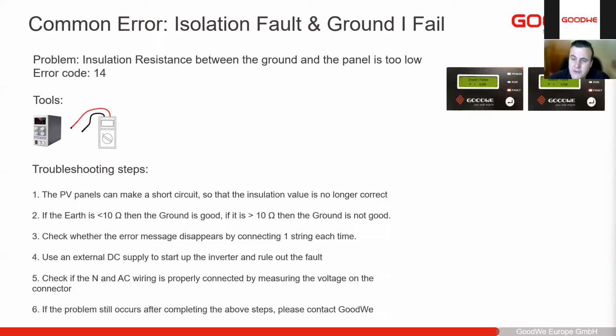We can also see whether the error message disappears. If you only connect one PV string at a time, you can also test multiple MPPTs on the device and see whether that disappears. If it's on one specific string, then you can be certain of where that fault is. I said external DC power supply to start the inverter up to make sure that the inverter is not faulty.